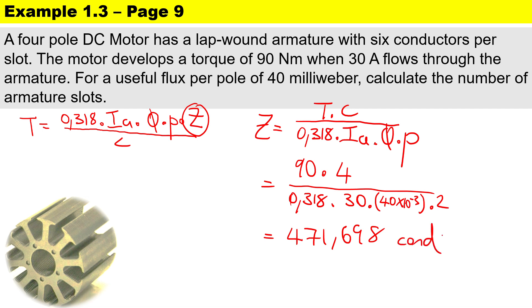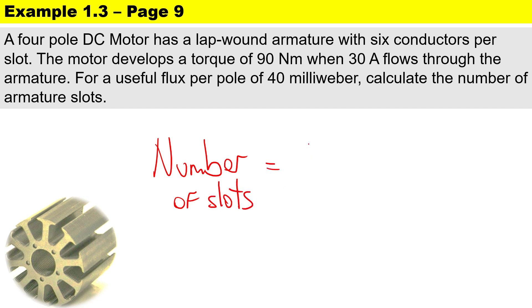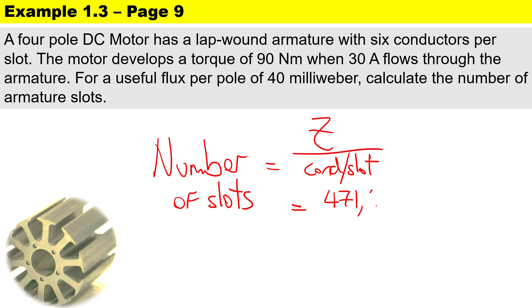Now we need to solve for the number of slots. The number of slots equals z (the total number of armature conductors) divided by the number of conductors per slot. Z is 471.698, and there are six conductors per slot, so the number of slots equals 78.616.